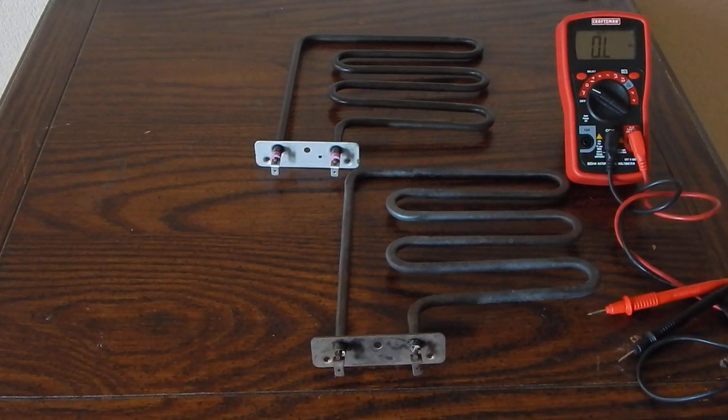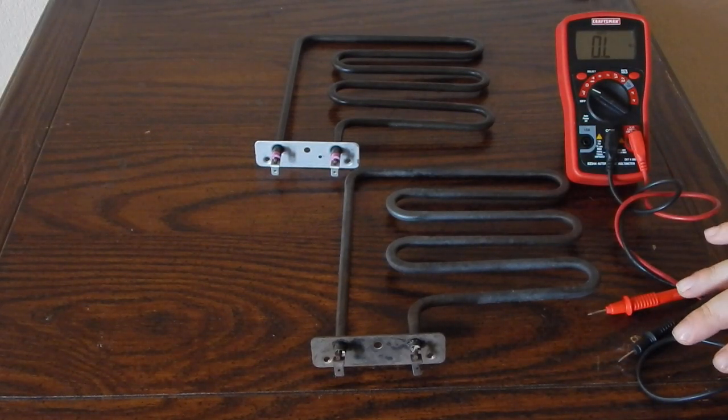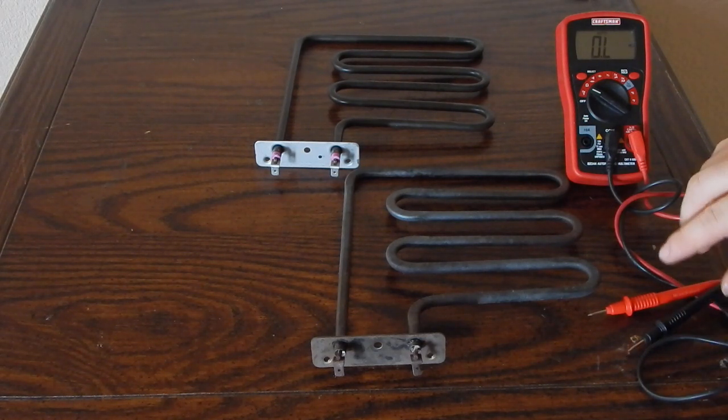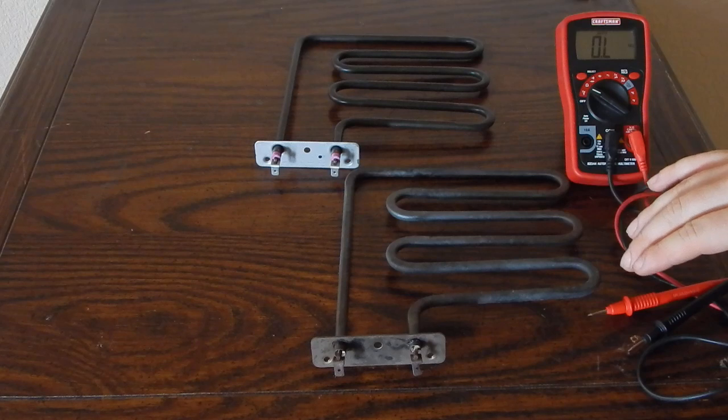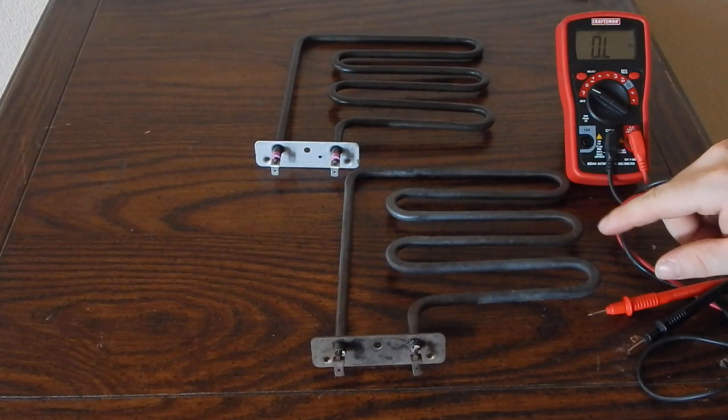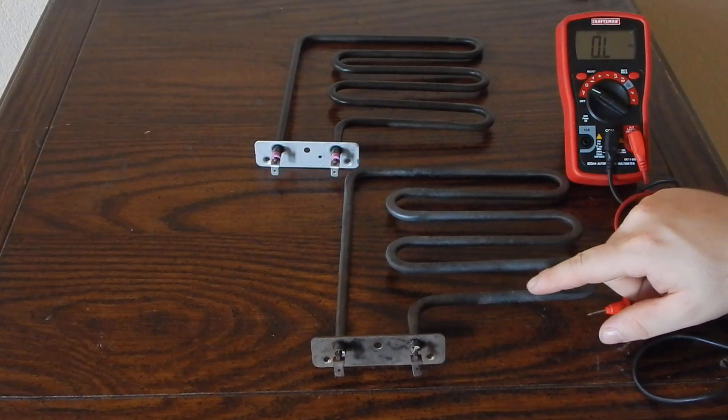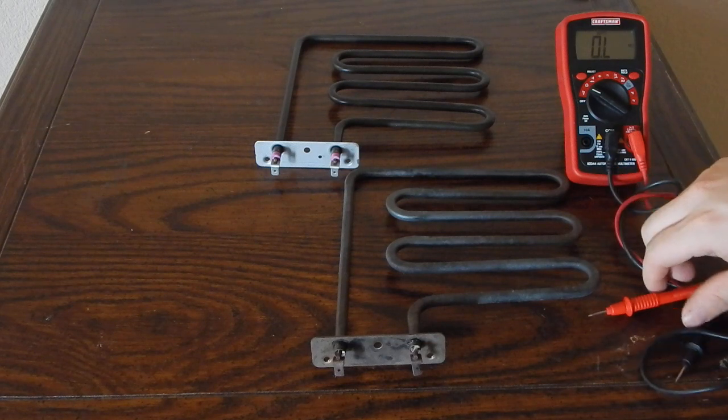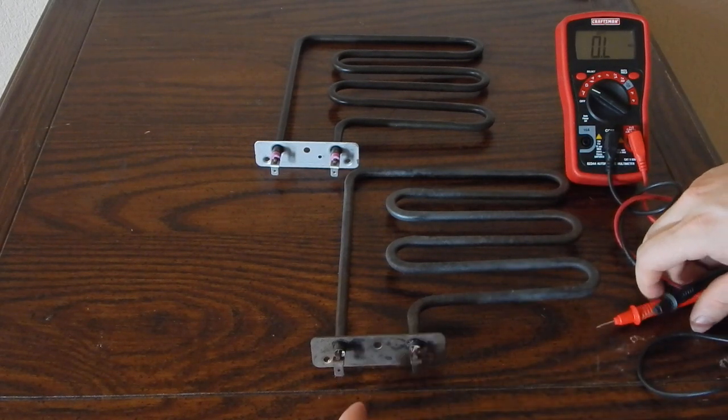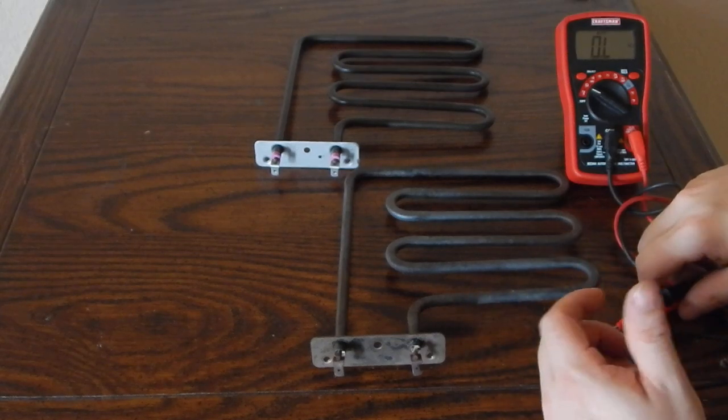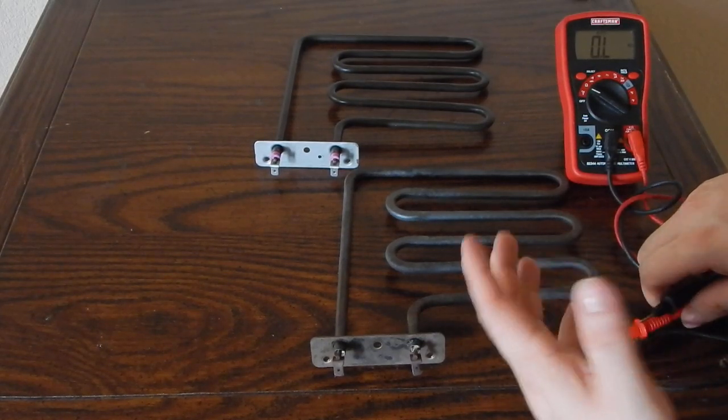So the heater element is made up of basically three parts: you've got the internal wire which is usually nichrome, then a ceramic or electrically insulating material, and then usually some sort of stainless steel or similar covering on the outside. What happens is electricity flows through that nichrome wire and it acts like a big resistor, heats the whole thing up kind of like a light bulb and creates the heat.